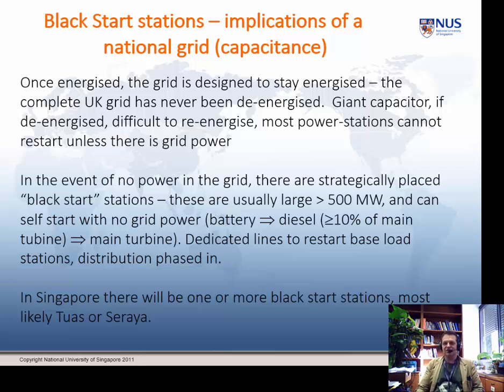But what happens when the power does go out? Your power stations just can't come on because it's the grid that powers the transformers and everything else. Now, there is some residual capacitance, but Singapore shares this with the UK. They have what are called black start stations. They're usually large stations and they can self-start with no grid power. In New Zealand they have them as well. They're diesel engines that start from battery. In the UK, they are hydro pumped stations that can just open and start generating.